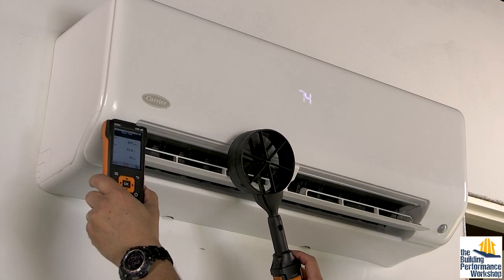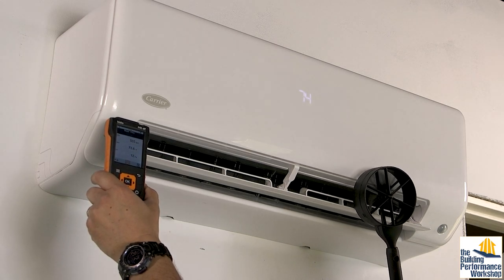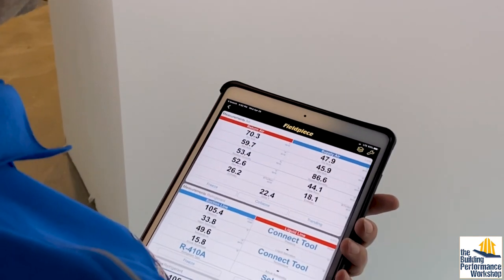After installing anything in a home, we like to test it to make sure it's doing what it says it's designed to do. We test the temperature split with a thermometer hygrometer on the return and supply sides while running one of the amazing apps available to technicians nowadays. Now we know for sure we're done. Subscribe to stay tuned to our channel for more information about the science of homes, and give us a thumbs up or comment below to share your successes and struggles with systems like these. You can also learn more about this new Carrier unit in the link below.